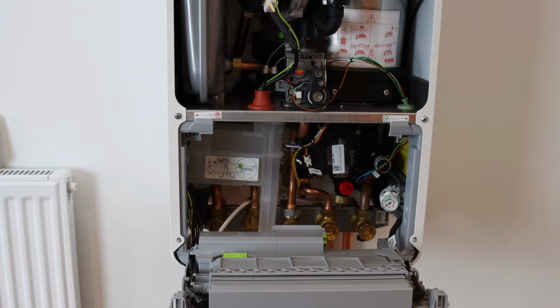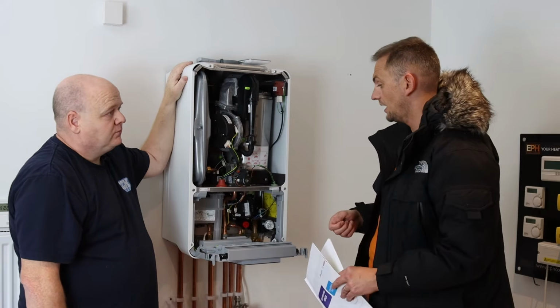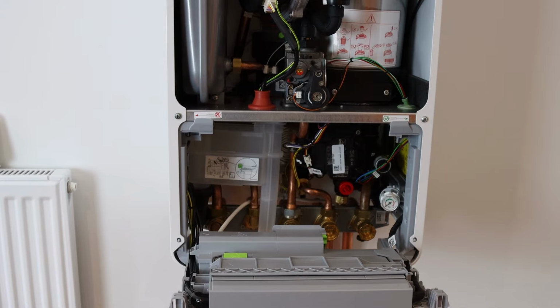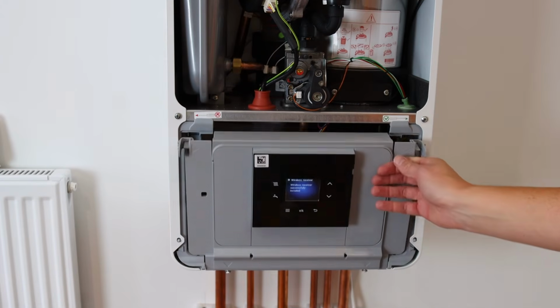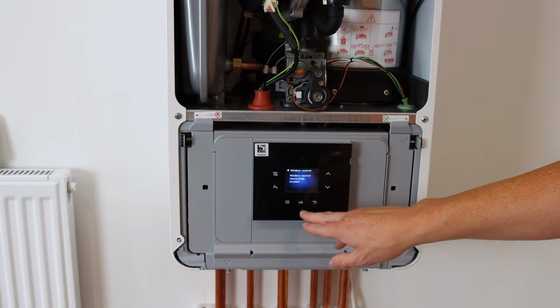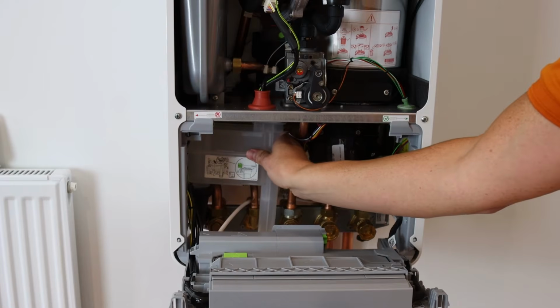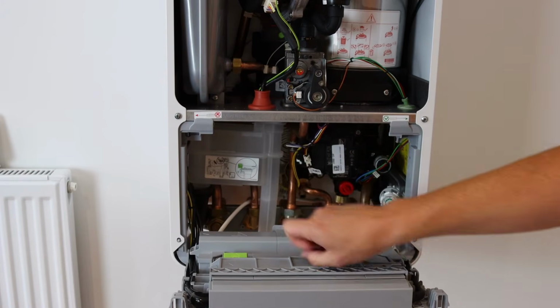If your boiler's passing a little bit of water, which happens to the best of us with age, you can easily replace the PRV, whereas the plastic is a nightmare. Same with the plate heat exchanger. Once you take the condensate trap out, which comes out with one screw, it comes out nice and easy.